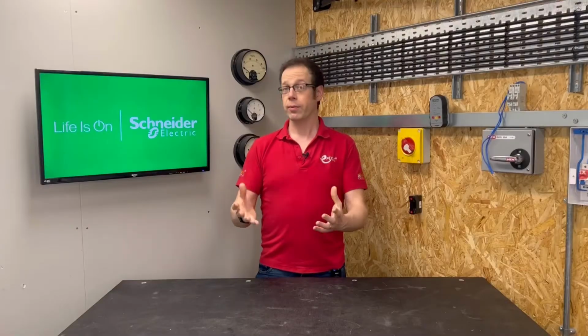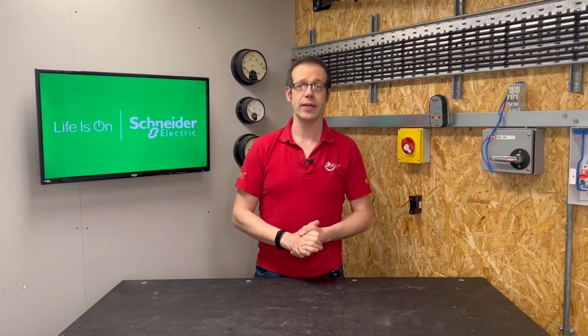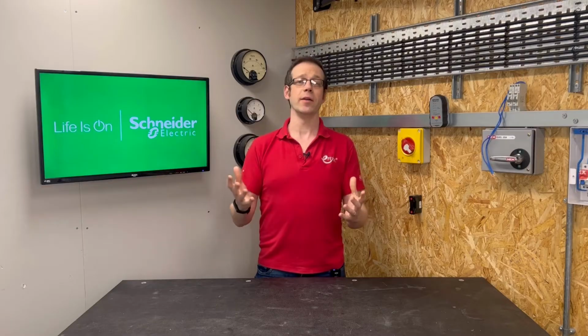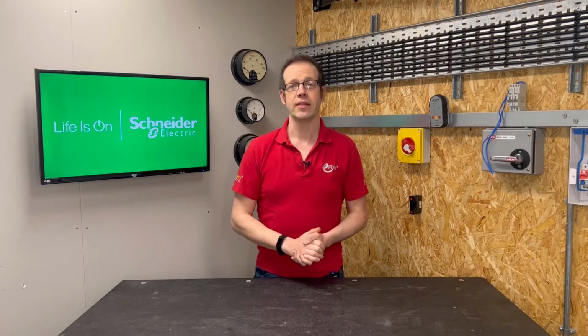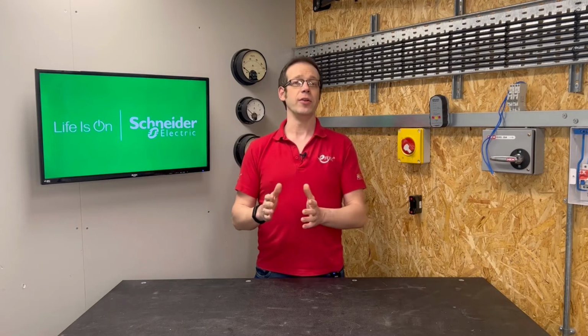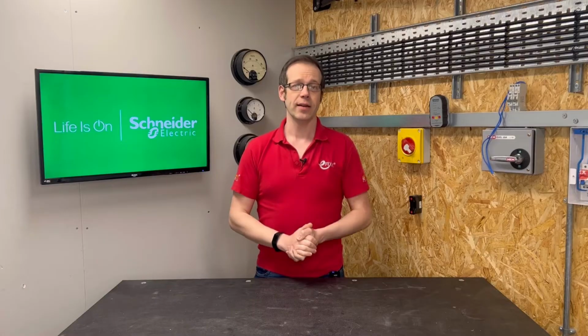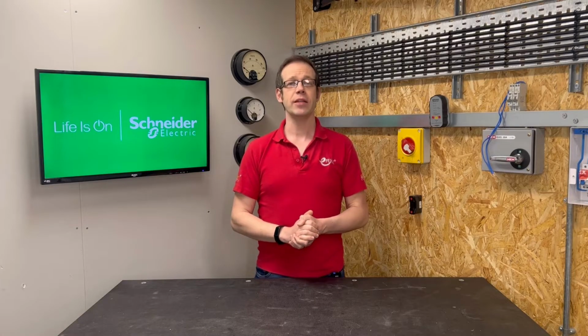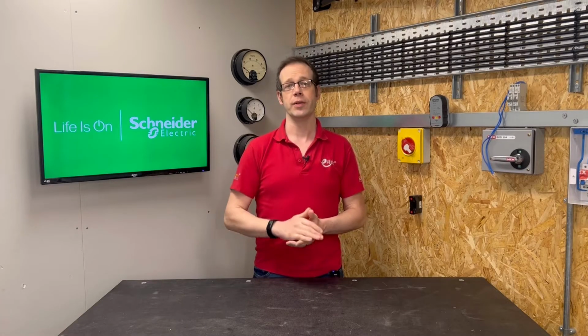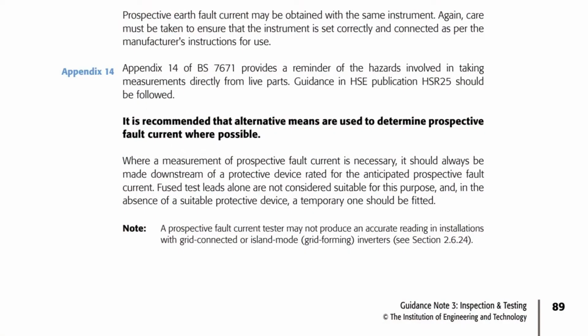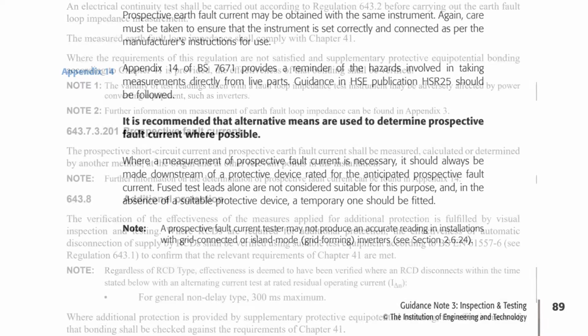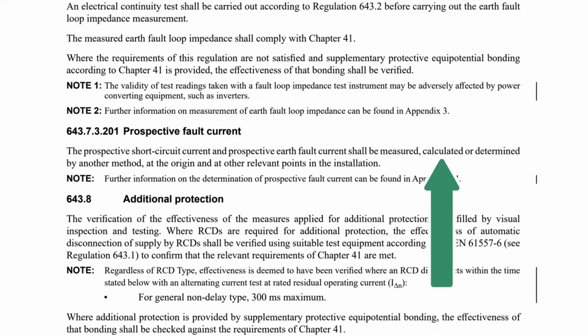When you're working with a three-phase supply, the worst case scenario is a simultaneous fault between all line conductors. An approximation of this can be found by measuring between the line and neutral conductors and doubling the highest value obtained. Again, this should be compared with the rating of your protective device. Guidance Note 3 includes the recommendation that alternative means to measurement are used to determine prospective fault current wherever possible. The second option given is calculation.